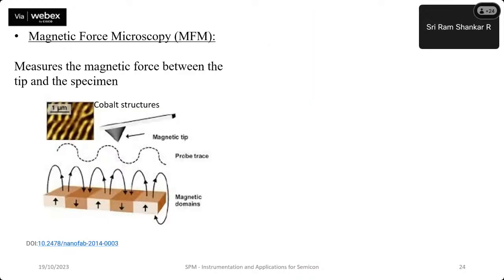In magnetic force microscopy you have this AFM tip, but the tip is coated with a magnetic material. Imagine that your sample is magnetic, but the magnets are of different orientation, either north and south and so on. So if you bring this magnetic tip close, firstly you need to know the topography of such a sample. Once you know the topography, you bring the tip close to the magnetic material, and based on the changes in this magnetic force you can infer whether it is of the same polarity or a different polarity and so on. With this you can characterize the grain boundaries in ferromagnetic materials and so on.